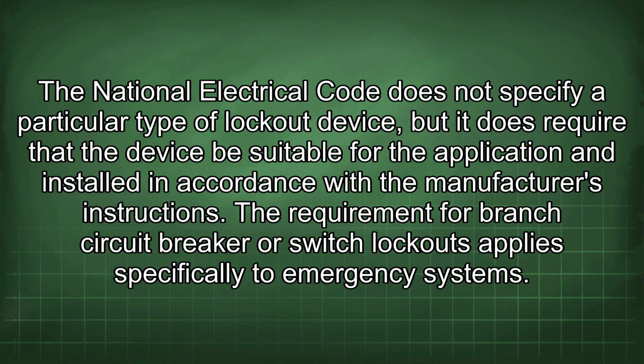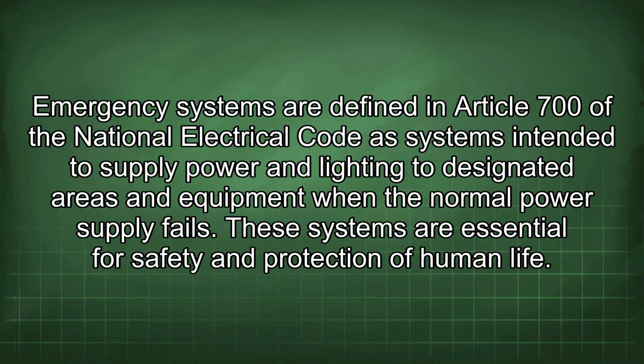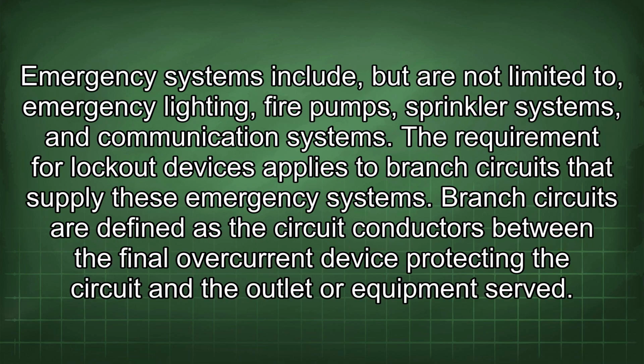The requirement for branch circuit breaker or switch lockouts applies specifically to emergency systems. Emergency systems are defined in Article 700 of the National Electrical Code as systems intended to supply power and lighting to designated areas and equipment when the normal power supply fails. These systems are essential for safety and protection of human life. Emergency systems include, but are not limited to, emergency lighting, fire pumps, sprinkler systems, and communication systems.